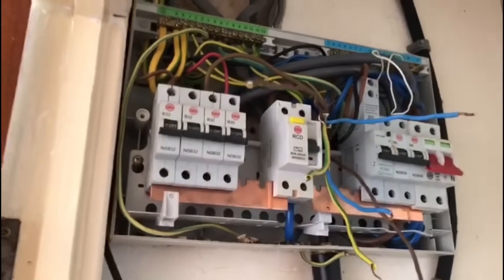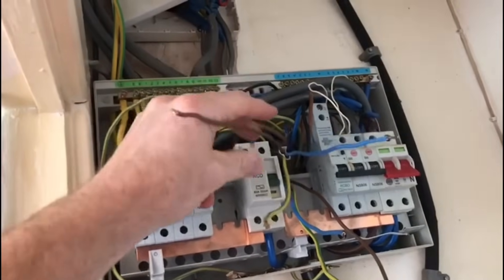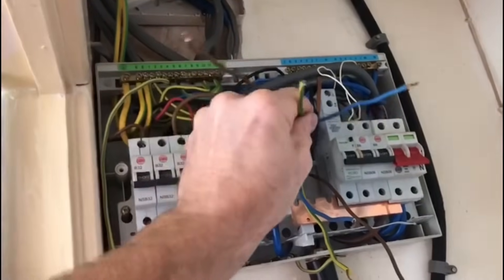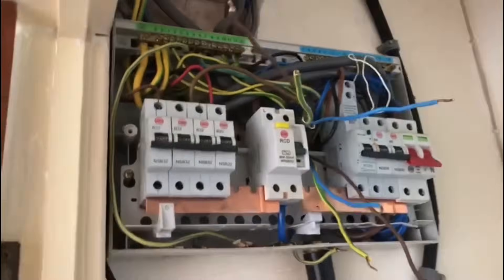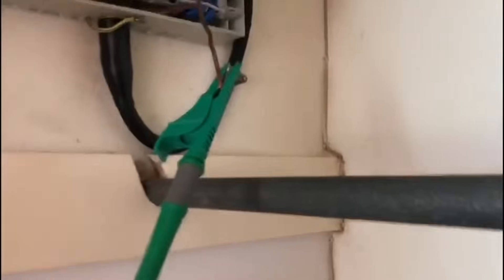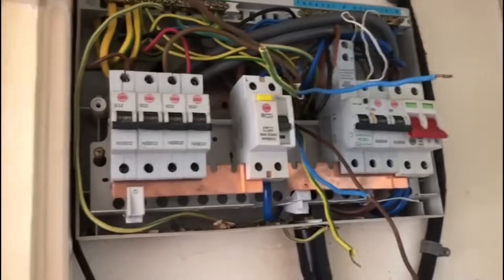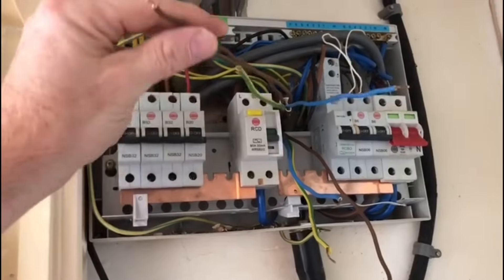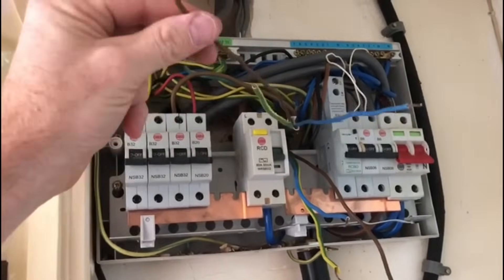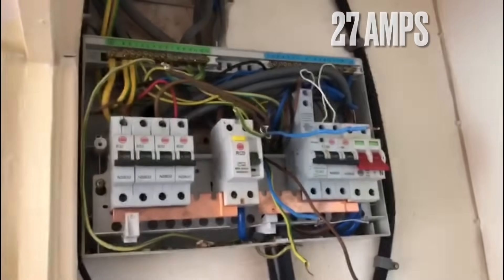We've got a 32 amp circuit breaker controlling what is in effect two radial circuits, not a ring circuit. These are only 2.5mm cable, so we need to downgrade this 32 amp to a 20 amp. I do have a spare 20 amp Wylex circuit breaker. One of the things I'll be doing on this EICR is taking the 32 amp out and sticking the 20 amp in — at least then the cable is better protected, since 2.5mm cable is only rated at about 25 amps.